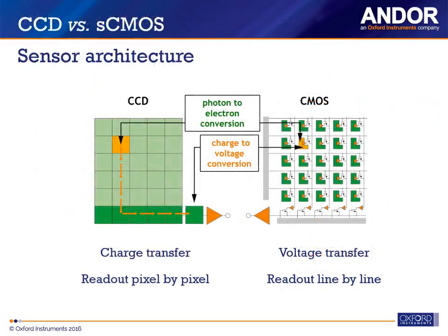So let's briefly touch on the fundamental difference between the readout of a CCD versus that of a scientific CMOS. So we've already described CCD readout in reasonable depth, but it's defined by this row by row, pixel by pixel serial readout nature, and therefore it's relatively slow as a consequence. CMOS or scientific CMOS, in direct contrast to that, is highly multiplexed, highly parallel in its readout mechanism.